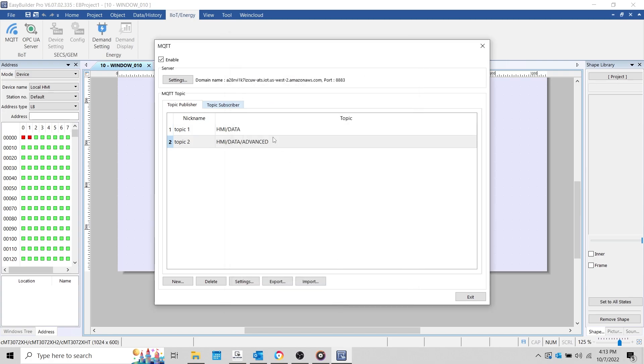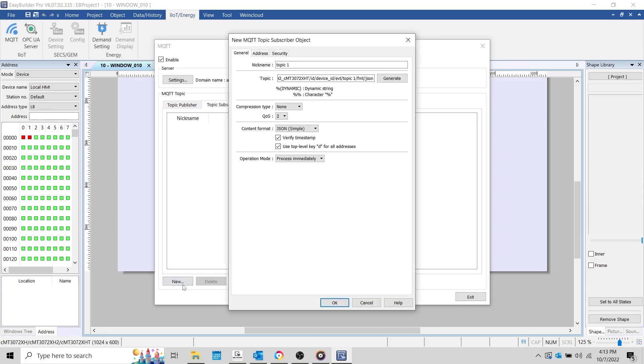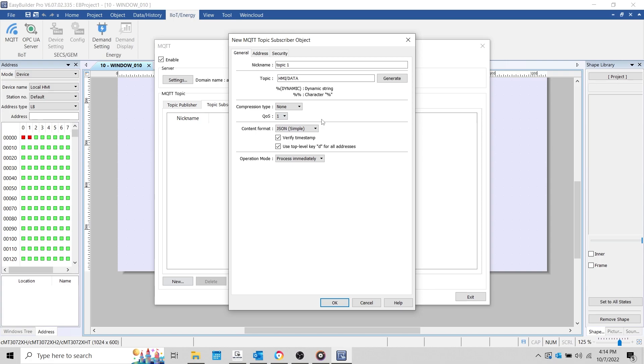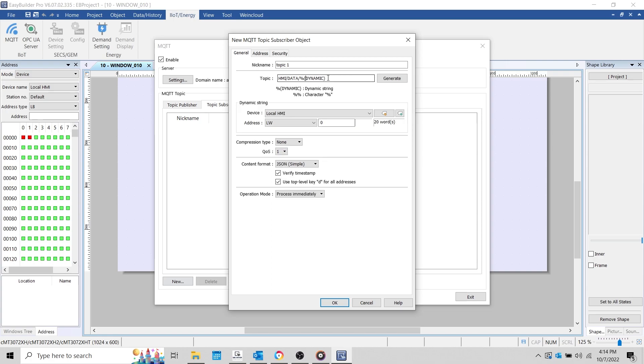Now, let's subscribe to an existing topic. To do this, we'll select the Topic Subscriber tab and click New. Since this is the only device that I have that will publish to the broker, I'll subscribe to one of the topics that we've already defined. Although, typically this topic would be published by another device. This is also a great time to point out that it's possible to define a dynamic topic by name using the %Dynamic syntax. This will allow the MQTT object to reference the topic name from an external register, which in turn will allow you to modify the topic name during runtime.